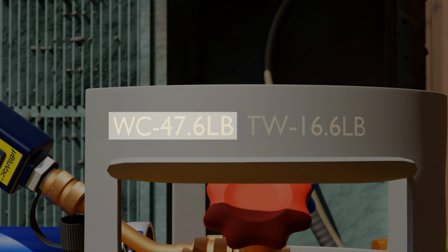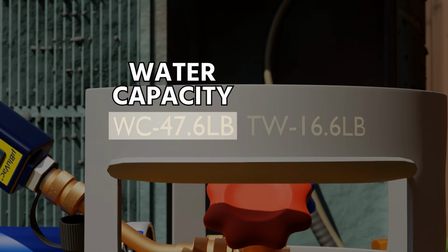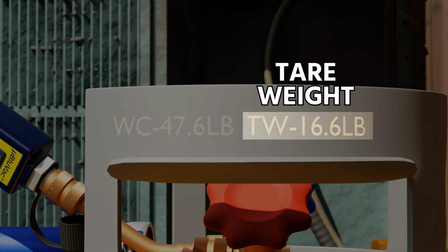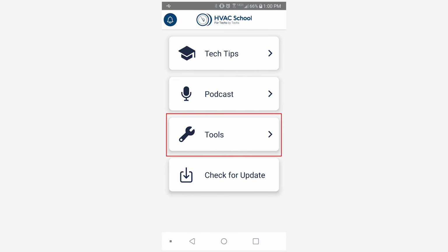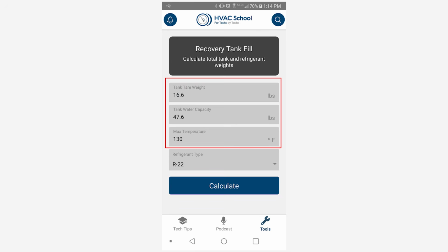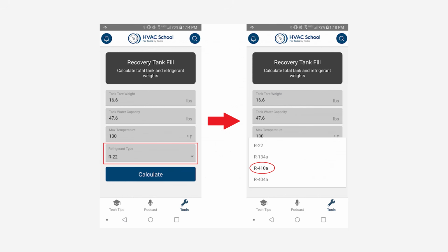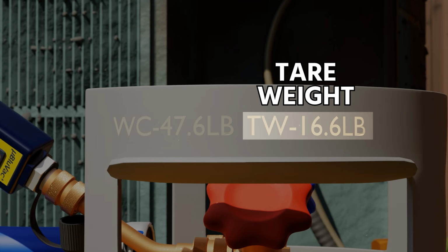Take note of the WC, or water capacity, of the tank. That's the amount of water a tank can hold. Also the TW, or tare weight, the empty weight of the tank. In order not to overfill a tank, we suggest using the recovery tank calculator on the HVAC School app or similar. For example, if this tank is empty, it will only weigh about 16.6 pounds because that's the tare weight or empty weight.